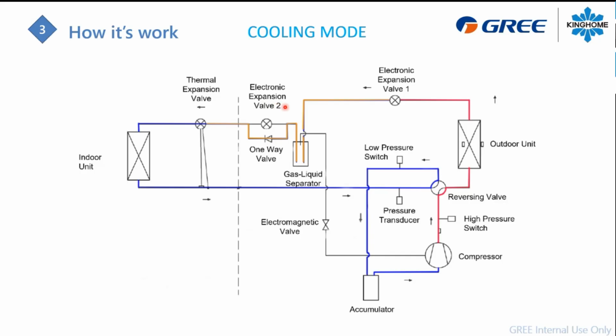So we will not use the electronic expansion valve number 2. We're going to see in heating mode what this guy will do. But for now, we're going to hit that check valve. The refrigerant will take the easiest way to flow through it. So we will take that check valve, and then we will go to the indoor unit. Either if it's an air handler or only a case coil, any type of case coil, you will hit your metering device here in cooling mode. So it will be your TXV. After that TXV, you will have low pressure, low temperature refrigerant. So you're still in liquid. In the evaporator, you will absorb the heat, and then you will get low pressure vapor refrigerant right here.